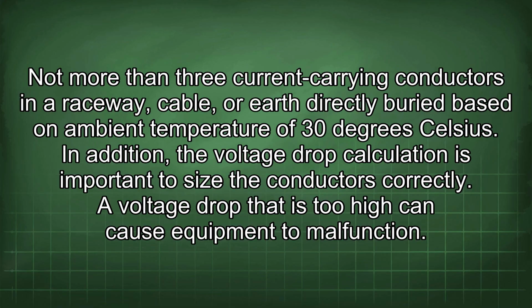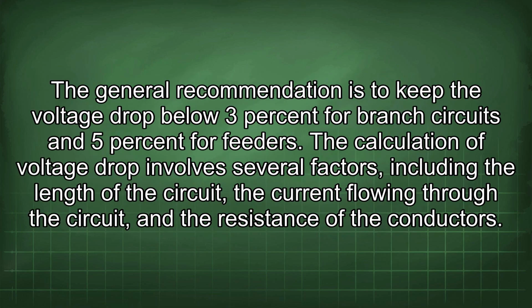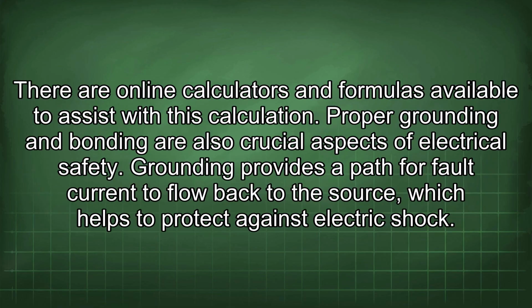In addition, the voltage drop calculation is important to size the conductors correctly. A voltage drop that is too high can cause equipment to malfunction. The general recommendation is to keep the voltage drop below 3% for branch circuits and 5% for feeders. The calculation of voltage drop involves several factors, including the length of the circuit, the current flowing through the circuit, and the resistance of the conductors. There are online calculators and formulas available to assist with this calculation.